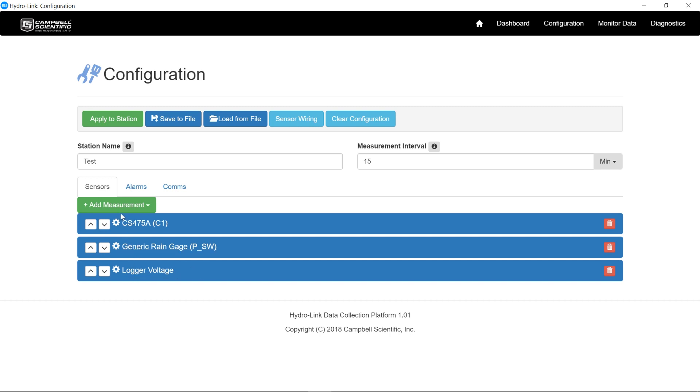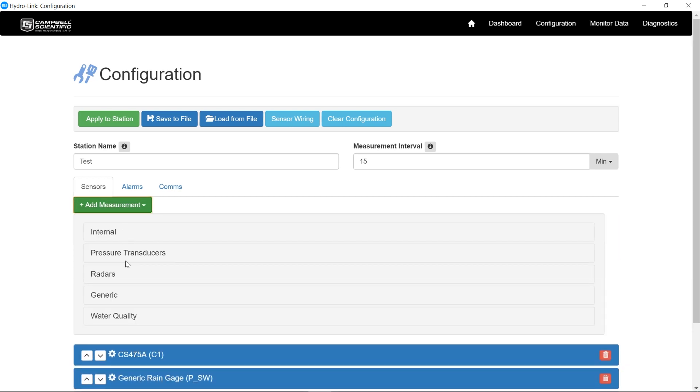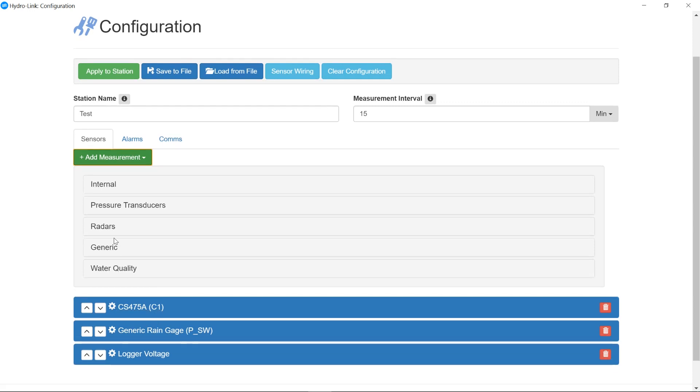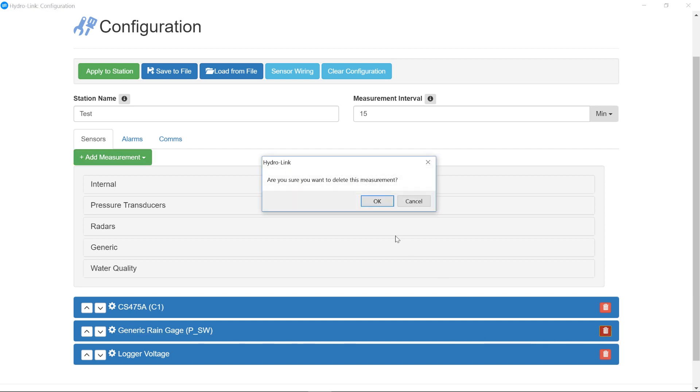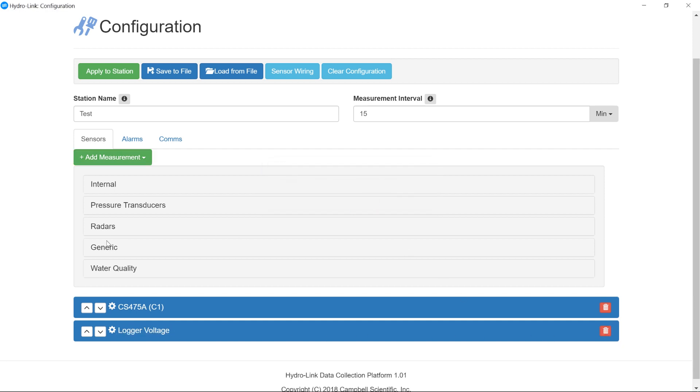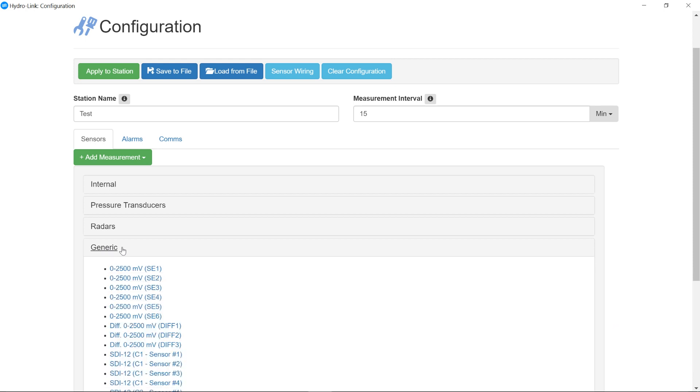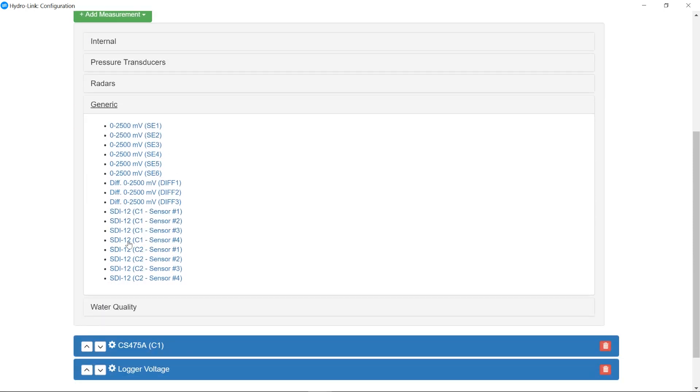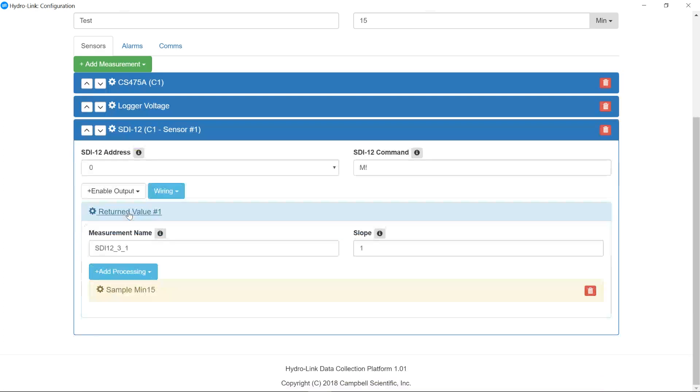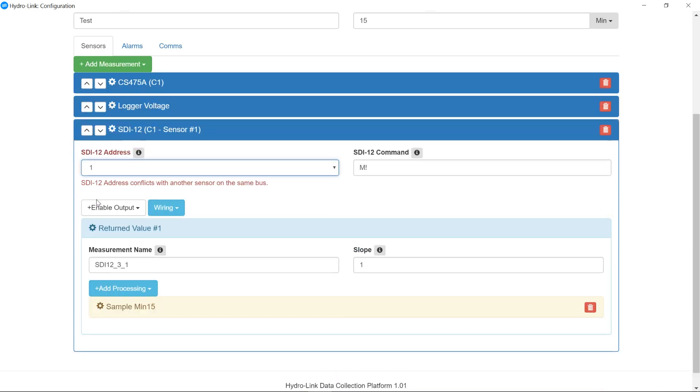Now, if you noticed in here where we added the measurements and we did the radar gauge, often you're going to be using sensors that are from other manufacturers and so you're going to have to use a generic. So what I'm going to do here is come in and add that same water level sensor but do it as a generic sensor. So I'm going to come over here and delete this one. Come into generic. SDI 12 on C1 address. So these setups are just very close to the same. I have to tell it now that it's generic I'm not quite sure how to talk to it. It gives me a little bit more options here. So an M command from SDI 12. So a standard M command for the measurement.